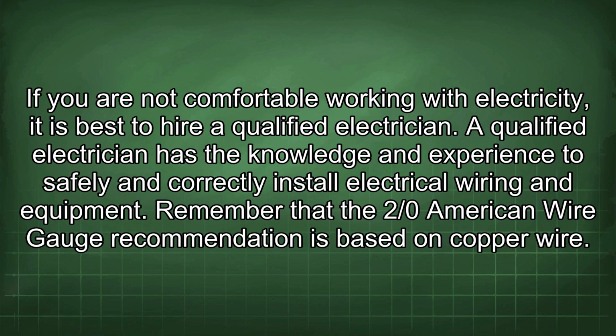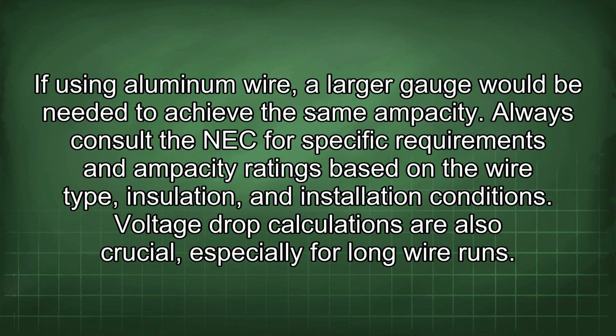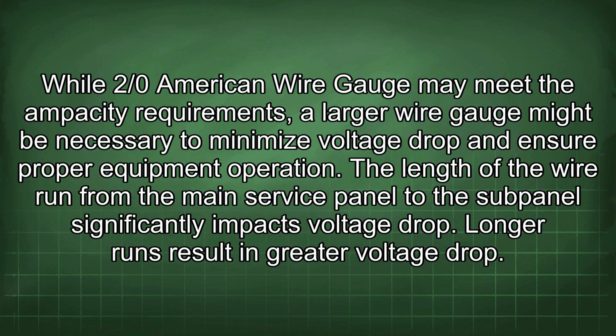Remember that the 2/0 American wire gauge recommendation is based on copper wire. If using aluminum wire, a larger gauge would be needed to achieve the same ampacity. Always consult the NEC for specific requirements and ampacity ratings based on the wire type, insulation, and installation conditions. Voltage drop calculations are also crucial, especially for long wire runs. While 2/0 American wire gauge may meet the ampacity requirements, a larger wire gauge might be necessary to minimize voltage drop and ensure proper equipment operation.